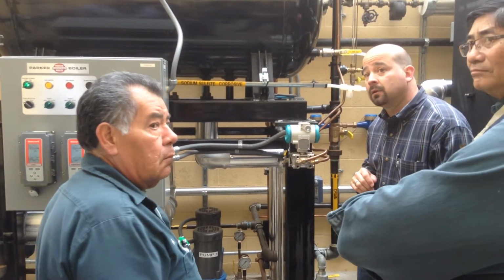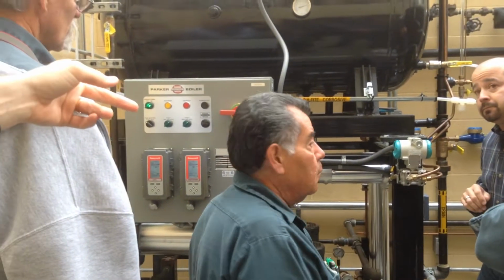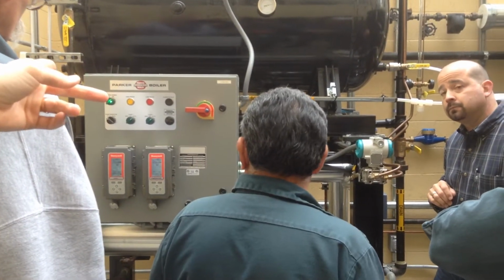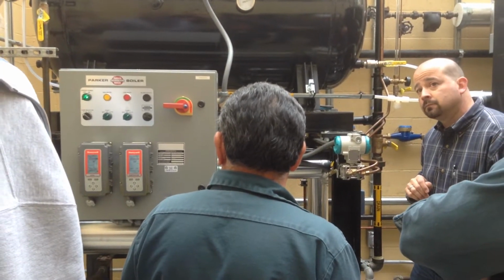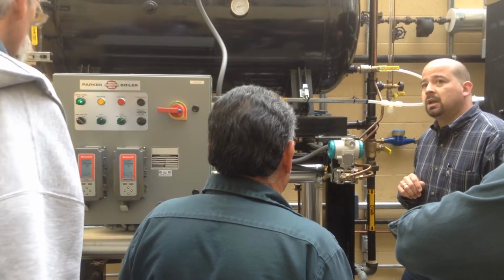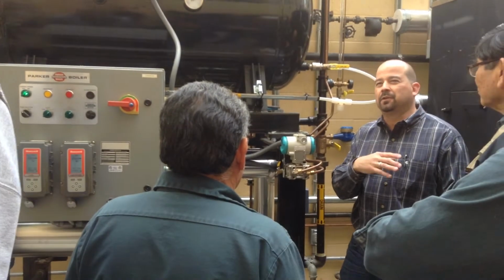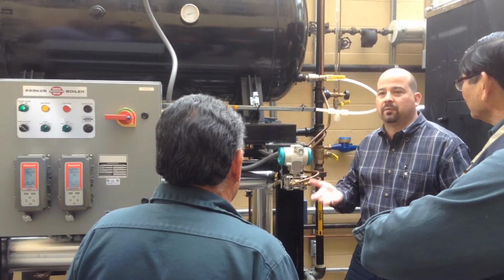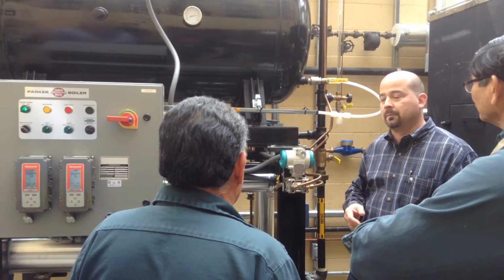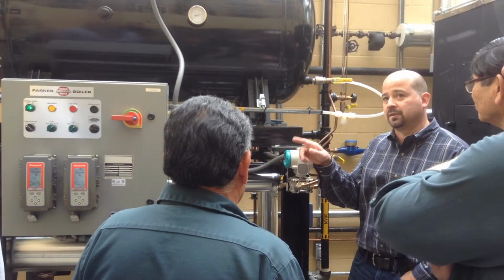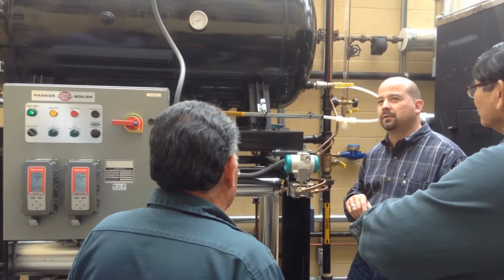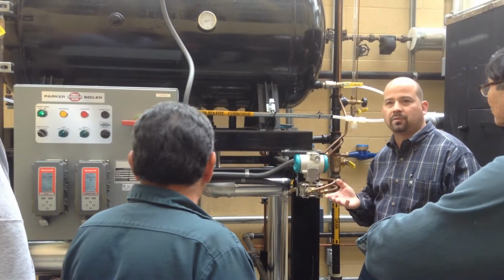Yes. So water level, two different sensors. One on the left, water level looks good. It's at 52%. The temperature right now shows 187. Is that too low? What should be happening? Depends on your load right now. If you don't have much of a load, but when you're under a heavy load, then it'll go up. I'd have to actually check the set point, which I'll do to see what it's set for. But most deaerators run at about 220, 212 to 220.